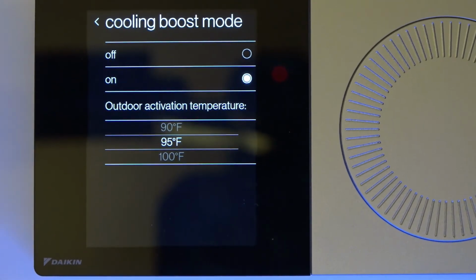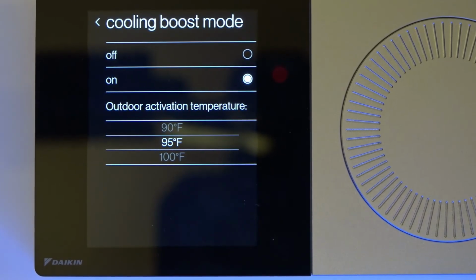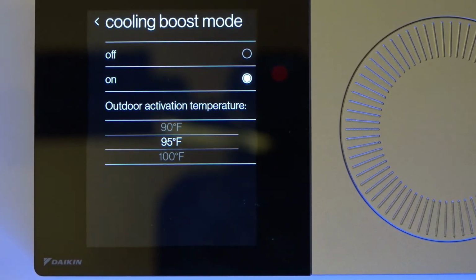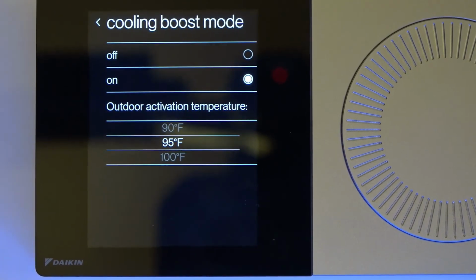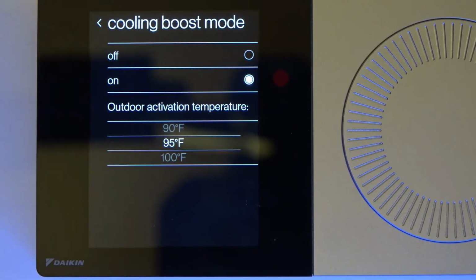What this does, when the ambient temperature sensor on the inlet side of the condenser coil reaches 95 degrees, the compressor is allowed to speed up and deliver roughly an extra 3,000 BTUs of cooling. So it holds a little bit back in reserve above its rated capacity, waiting on that hottest day. So it's able to deliver a little extra cooling there. So that's a pretty neat feature right there.